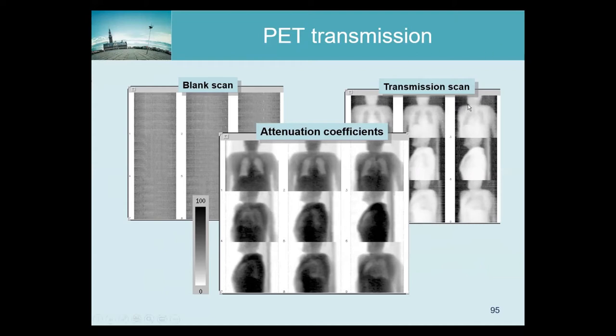Here is the transmission scan. You get high intensity outside the patient and low intensity inside the patient. That's a bit the tragedy of transmission imaging — the most important part is obviously where the patient is, and there you get the lowest number of photons and the highest amount of noise. You get an excellent measurement of the background, but nobody cares. Dividing the blank scan by the transmission scan produces the correction values, essentially turning low values into high values.